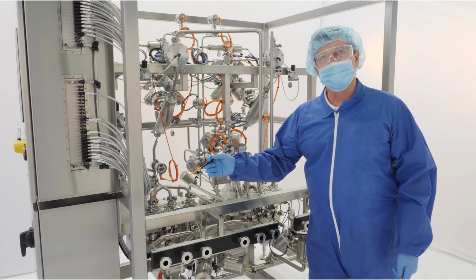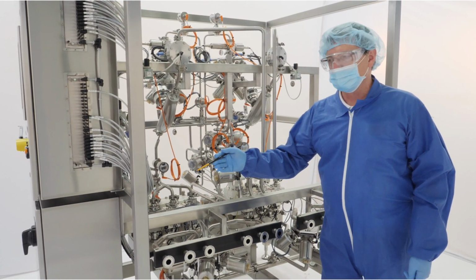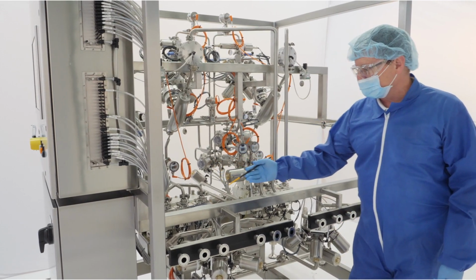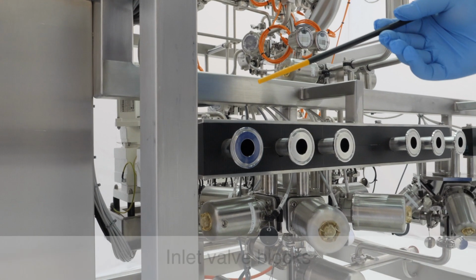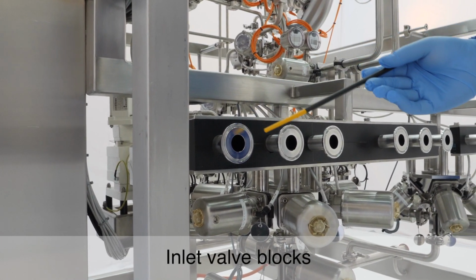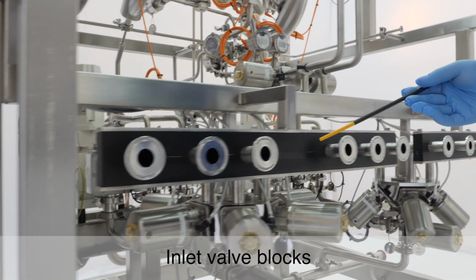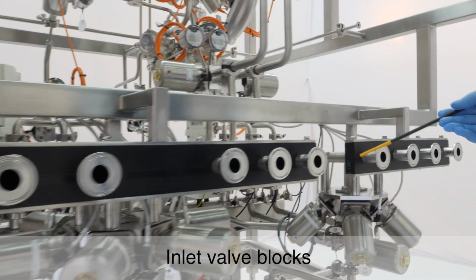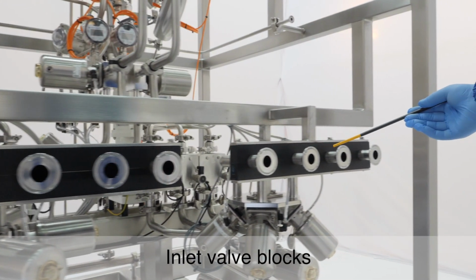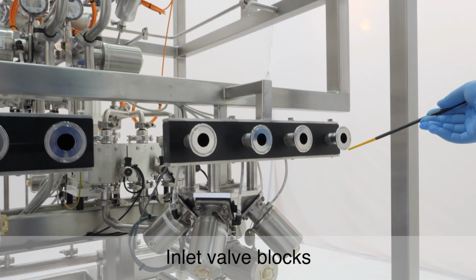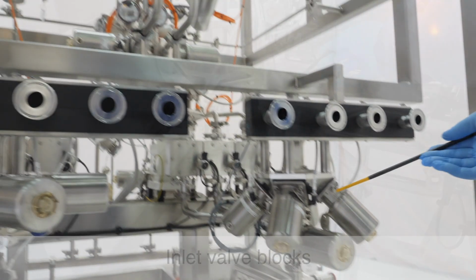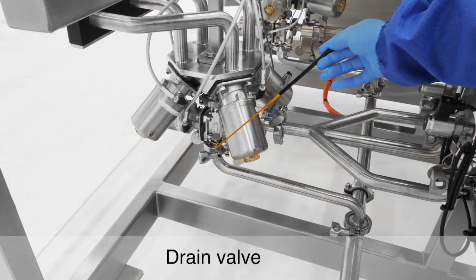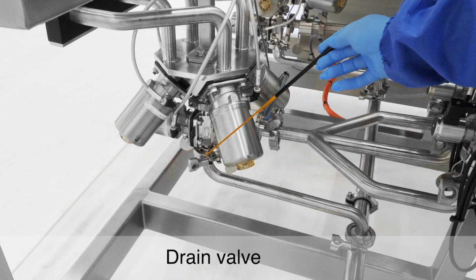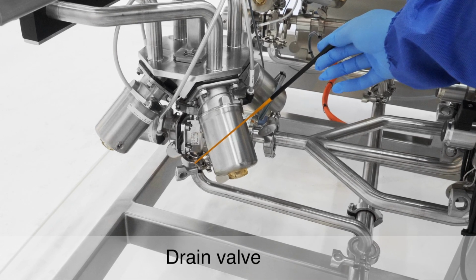The inlet valves are conveniently located at waist level. Now, looking closer at the inlet connection array, on the left, up to six different buffers are connected, leading to the inlet valve block of the buffer pump. On the right, the feed and up to three different buffers are connected, leading to the inlet valve of the feed pump. To ensure drainability on the suction side of the pump, drain valves are installed on the inlet valve blocks.